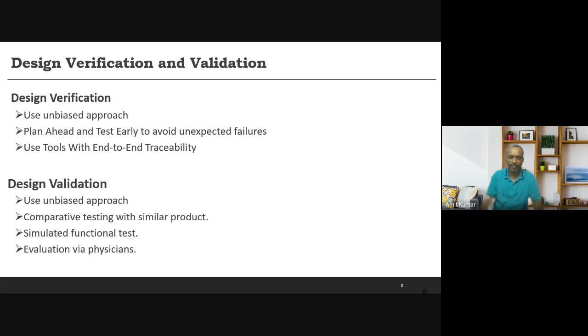We could go into detail like what is design verification, what is design validation. But when you are performing a design verification, use an unbiased approach. So what do we mean by unbiased approach? The typical tendency of any engineer is, let's try to pass it, let's try to meet what is asked of us. But the approach should be, when you say unbiased approach, it means I will not try to meet it. I will try to find out how it fails. I will not write a verification procedure which will make sure that the design requirement is met. But I will write a procedure in such a way that I should see a failure, or if there is a way to fail it, I should document it. So that's what we mean by unbiased approach.